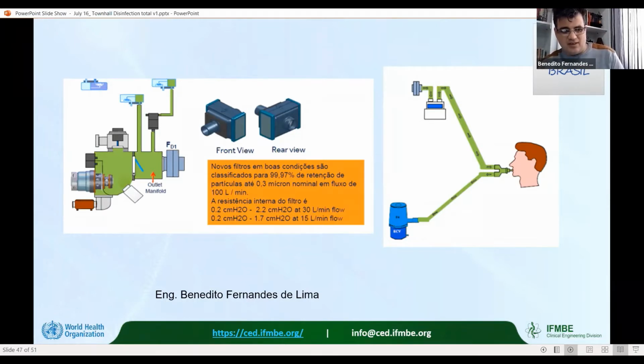When we started the sterilization process of the exhaling valve, we had a decreased valve lifetime and more liquid problems, and also more exposure of the clinical engineer team to contamination, considering that when there is a problem, the first assistance is done with the equipment working with the patient, and only after that do we take a better decision, which is to replace the equipment or try to solve the problem with the equipment connected to the patient. Bear in mind that there is not always other equipment available. Because of that, more training of the team is necessary. Next slide, please.